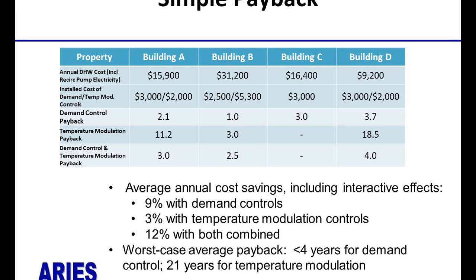So let's take a look at the simple payback. Here you can see for the 4 buildings, annual costs, including the recirc pump electric, range from about $10,000 to $30,000. And now inclusive of the interactive effects, the cost savings on an annual basis averaged about 9% for demand controls, only 3% for the temperature modulation, and 12% for both combined. And in the worst case scenario for the interactive effects that we showed in the previous slide, you're still getting less than 4-year payback for demand controls, which is pretty good, and 21 years for temperature modulation, which is not so good, especially considering these controls are typically said to have a useful life of maybe 15 years.